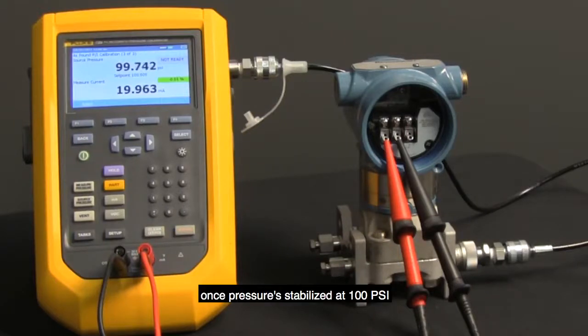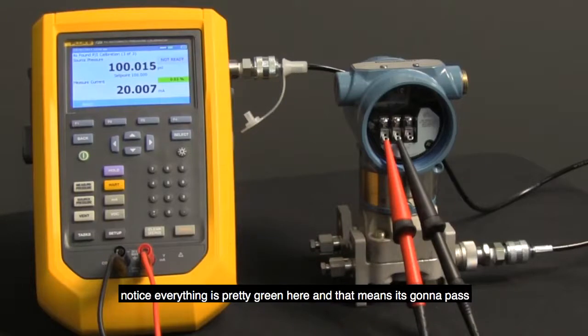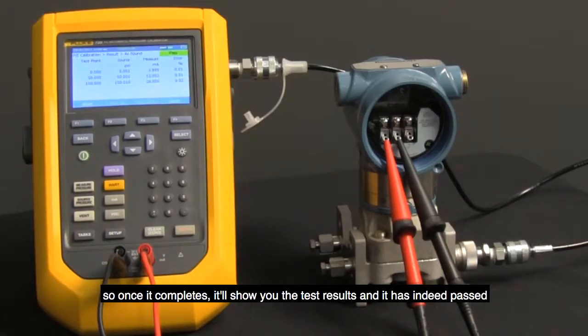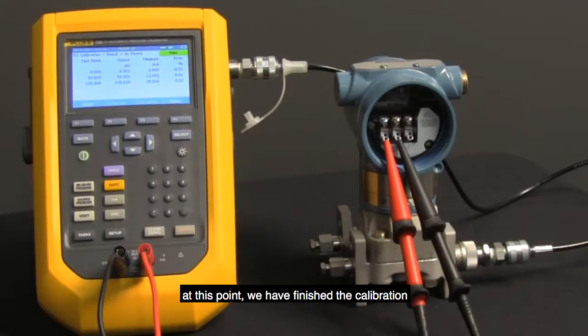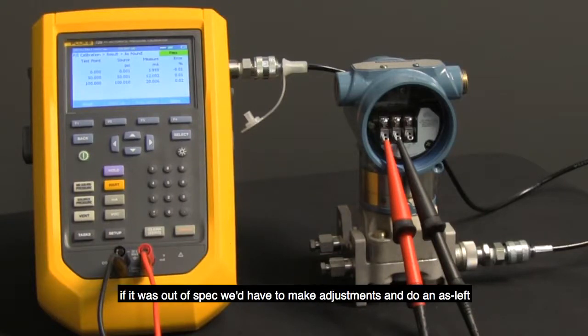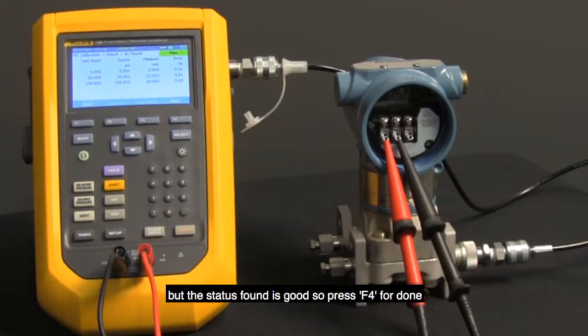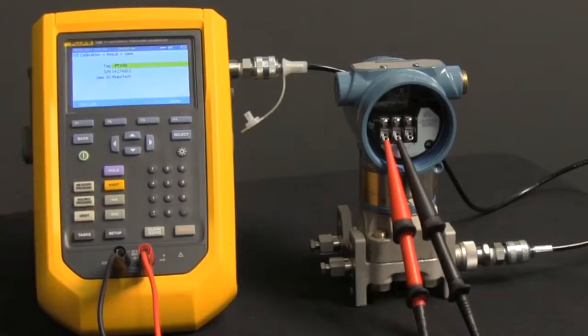Once pressure is stabilized at 100 psi, the 729 will document the 4-20 output, and notice everything is pretty green here, and that means it's going to pass. So once it completes, it'll show you the test results, and it has indeed passed. At this point, we have finished the calibration. If it was out of spec, we'd have to make adjustments and then do an as left, but this as found is good. So press F4 for done.